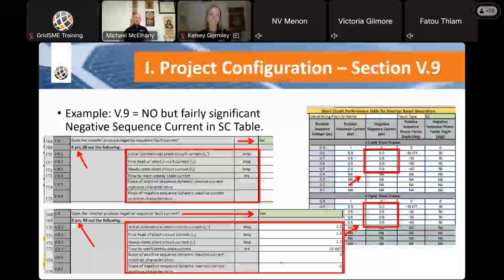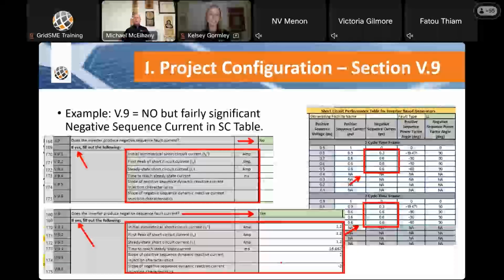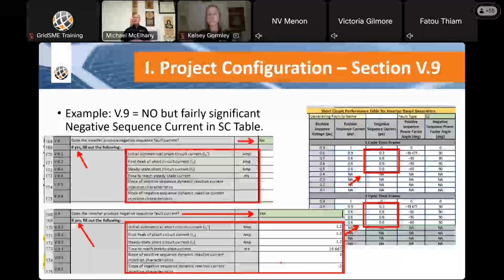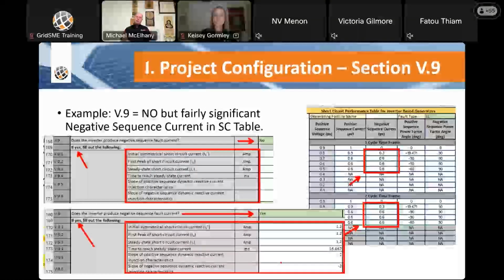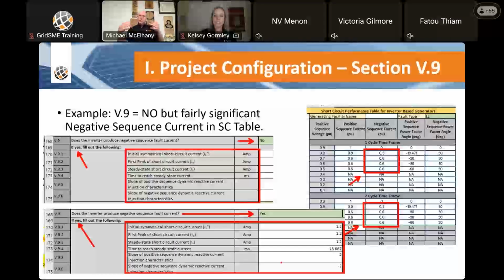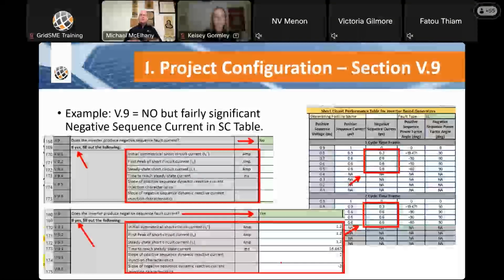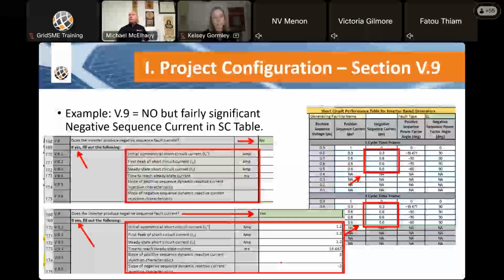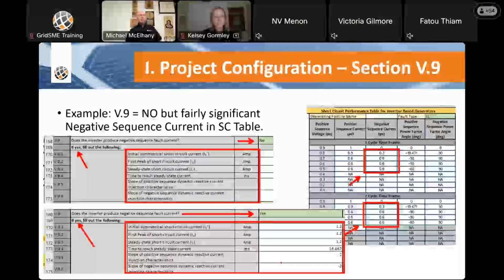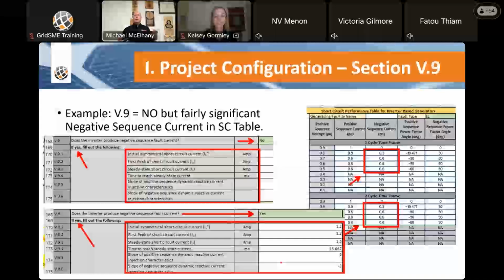But for line-to-line and single-line faults, if there is typically more than about 0.2 per unit negative sequence current, CAISO may ask the question, which again causes a delay. So we try to do a confirmation, whether it's a new inverter manufacturer, we get that confirmation. And it's a difficult answer because of the way the workbook is constructed.